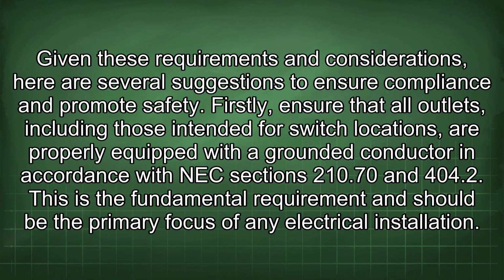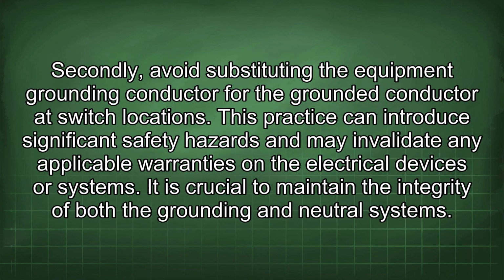Given these requirements and considerations, here are several suggestions to ensure compliance and promote safety. Firstly, ensure that all outlets, including those intended for switch locations, are properly equipped with the grounded conductor in accordance with NEC sections 210.70 and 404.2. This is the fundamental requirement and should be the primary focus of any electrical installation. Secondly, avoid substituting the equipment grounding conductor for the grounded conductor at switch locations. This practice can introduce significant safety hazards and may invalidate any applicable warranties on the electrical devices or systems. It is crucial to maintain the integrity of both the grounding and neutral systems.